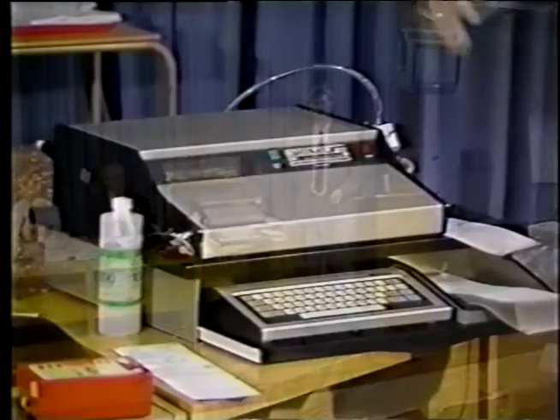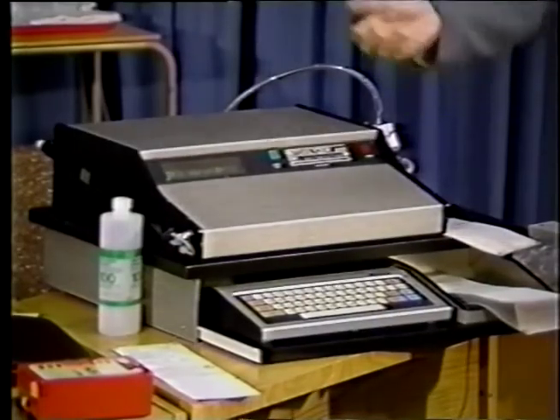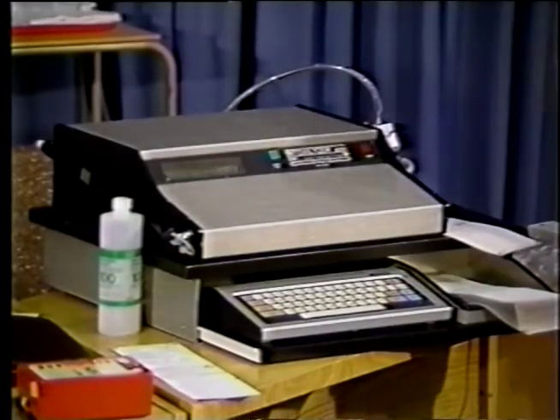The detection of alcohol is accomplished by using infrared light. Alcohol will absorb certain wavelengths of infrared light. So basically the instrument, using 3 wavelengths of infrared light, measures the decrease in infrared light as there's alcohol in the sample. If someone is blowing into the chamber and there is alcohol in the breath, there'll be a greater and greater decrease of infrared light, which will be processed into a blood alcohol concentration.